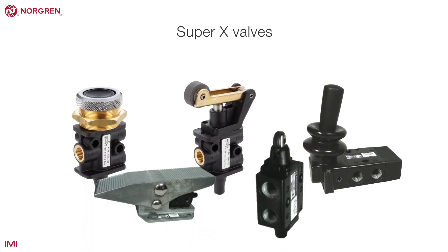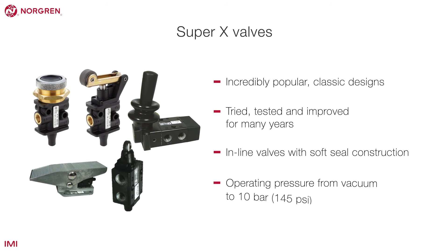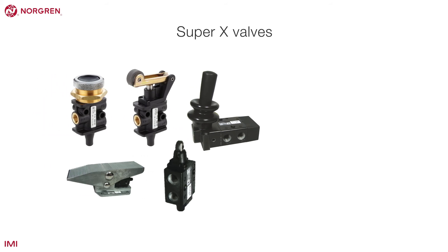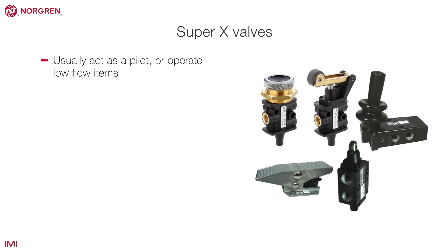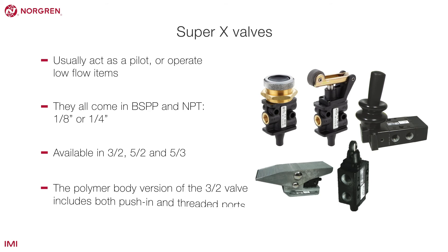Super X manual and mechanical valves are incredibly popular classic designs that have been tried, tested and improved for many years, making them extremely reliable. All are inline valves with soft seal construction and have an operating pressure from vacuum to 10 bar or 145 psi. These valves usually act as a pilot or operate low flow items. They all come in one-eighth or quarter-inch port sizes with BSPP and NPT options and a wide variety of manual or mechanical operators. These valves are available in 3-2, 5-2 and some 5-3 functions. The polymer body version of the 3-2 valve includes both push-in and threaded ports.